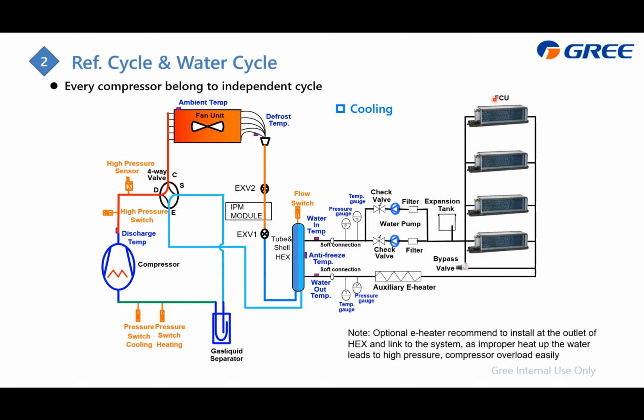Now just focus on the water cycle. The water cycle is regular. We have the expansion tank and water pump, and also before and after this tube and shell heat exchanger, we use temperature and pressure gauges to check the temperature and the pressure. And this is the FCU, just for example. So the water coming out from the water pump will flow to this one to be cooled down, and coming out will be the chilled water, right? This chilled water will go to the FCU to absorb heat, which ensures the temperature does not go so high, and then the water comes out and flows back to the water pump.